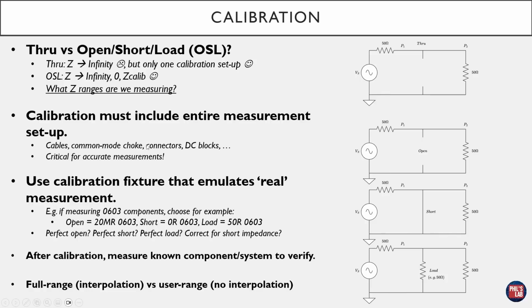Another thing is, how do you set up your calibration fixture? Your calibration fixture should emulate your device under test. That's the real measurement you'll be doing on your device under test. So if I'm measuring 0603 components, I'm not going to choose a short or an open that looks like a 1206 component. So you might want to choose your calibration fixtures to have the same physical dimensions and properties as your actual device under test. One other problem is, of course, there's not really a perfect open circuit, there's not a perfect short circuit, and there's not a perfect load. We'll have tolerances, contact resistances, and more, which, especially for low impedance and high frequency measurements, you might have to correct for.